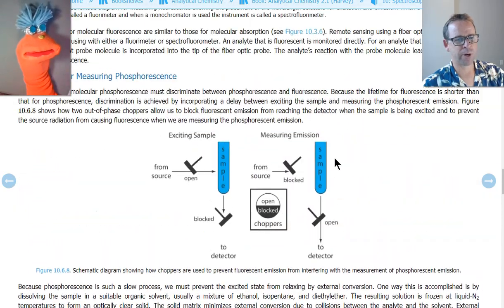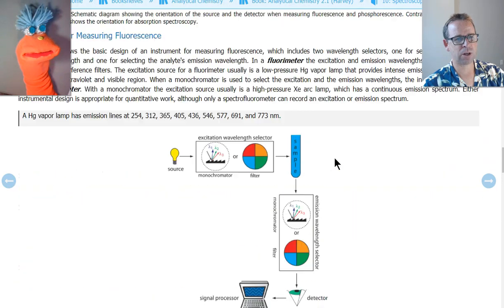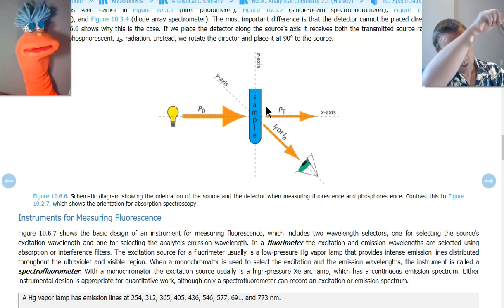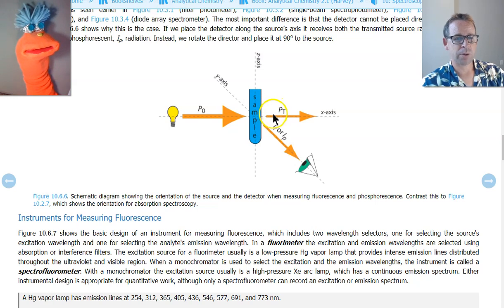Okay, for fluorescence, because of the extra movement of light, so here on absorbance, the light travels from here and goes out there. But for fluorescence, the light will travel here and come out here, and the fluorescence of samples will differ significantly from one to another. So you can have some molecules which are hundreds of thousands of times more fluorescent than other molecules, whereas usually that absorption range is not so vast. Because of that, you have varying slit widths, the slit that allows the light to come into your sample, and the slit that is collimating the light coming out of your sample.